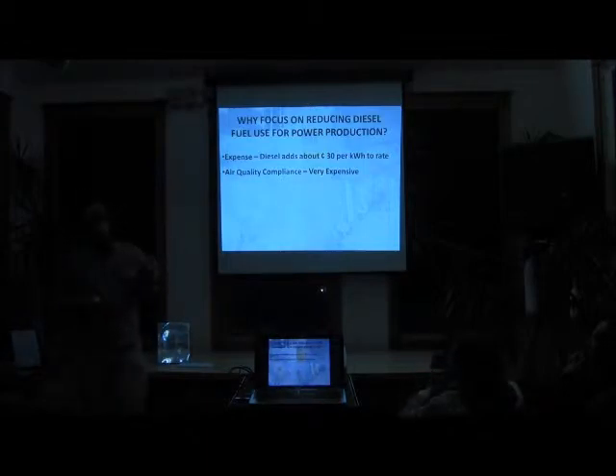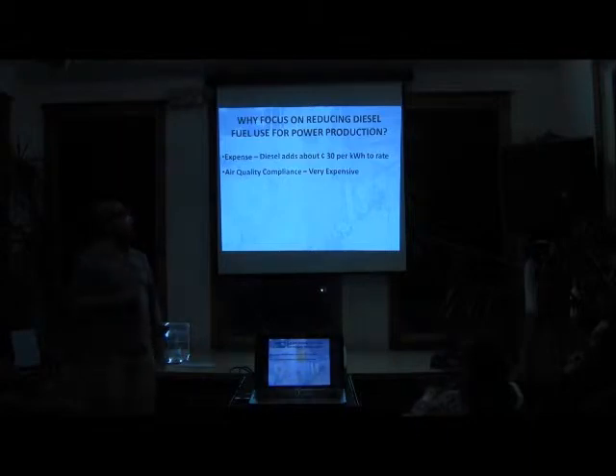Once we go over 12 megawatts, if we have to add another diesel generator to cover the load growth in the summer, we have to go to a Title I permit, which costs about 3 to 4 times more than the Title V permit, which is already pretty expensive. And it takes about 2 years to get the whole permit done, and you have to have lawyers, and it's a big pain in the butt.